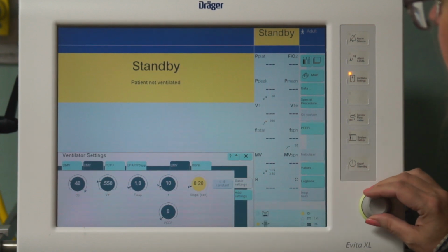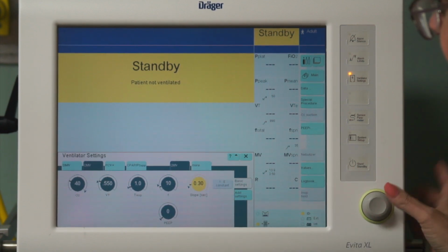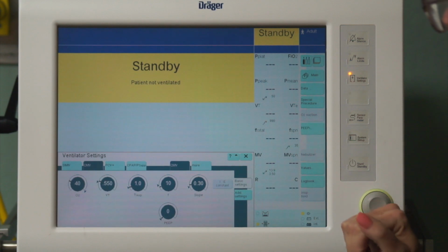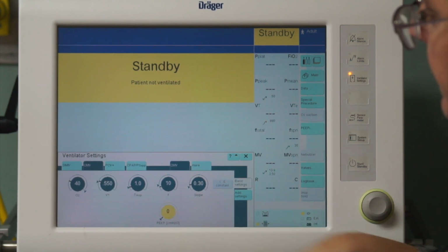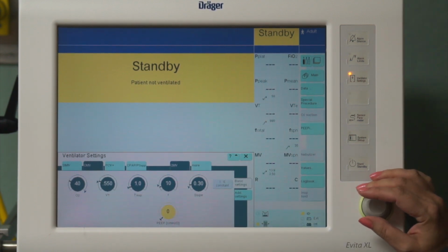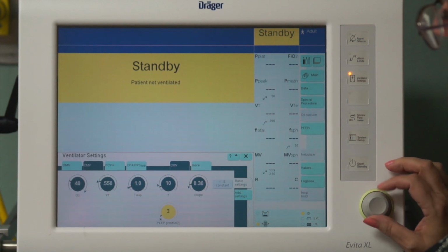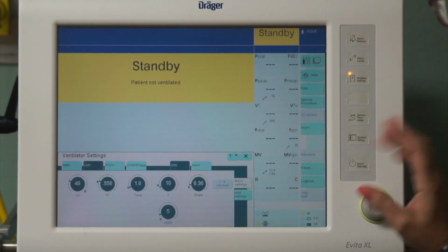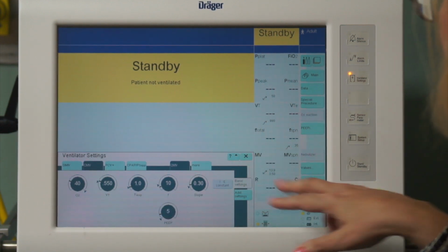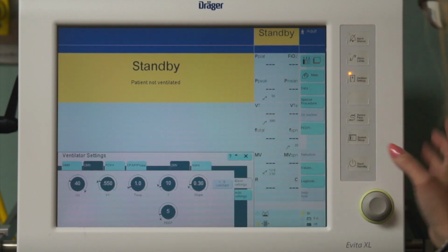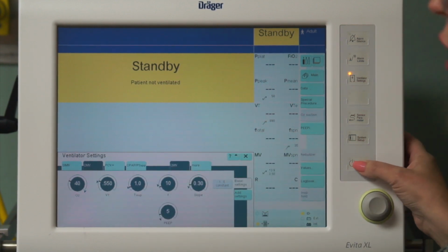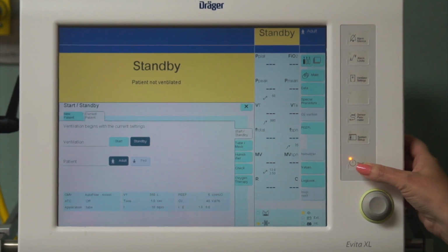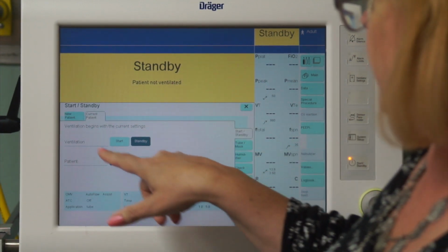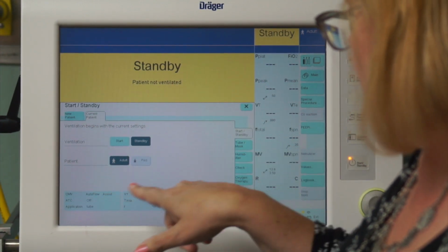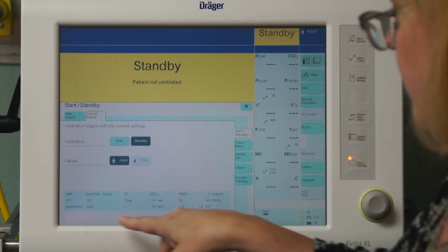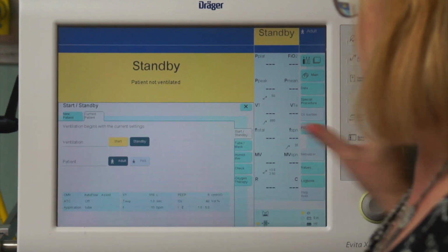Our slope, this is how fast our volume is going to be delivered. We'll just set that according to your patient scenario. And our PEEP, it's preset to 0, so do not forget to set your PEEP. You're going to want a PEEP of 5 here. Okay, so once I have all those settings on there, I'm going to go ahead and press the start button. It'll get me back to this screen, and these are all the settings I just chose, and I'm going to go ahead and press start.